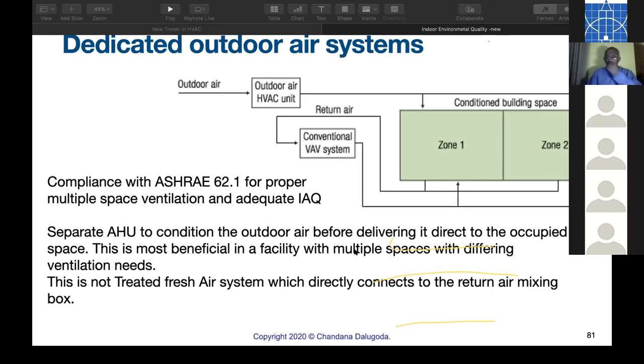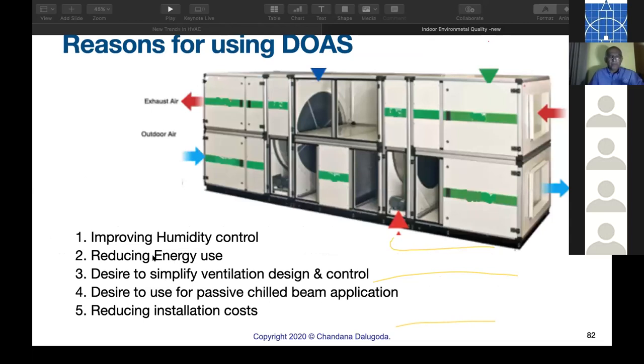So, as per this figure, outdoor air is handled separately. Conventional system handles internal loads separately. That is the basic of a dedicated outdoor air system. Now, this is a dedicated outdoor air handling unit that improves humidity control, reduces energy, simplifies ventilation design and control, is used for passive chilled beam applications, and yes, reduces installation costs also. Now, this is the last, this I will explain and we'll come to the end of the presentation, but this is quite an important thing.